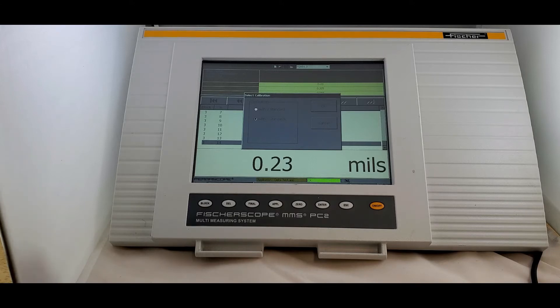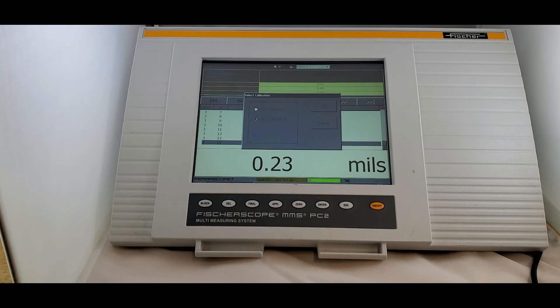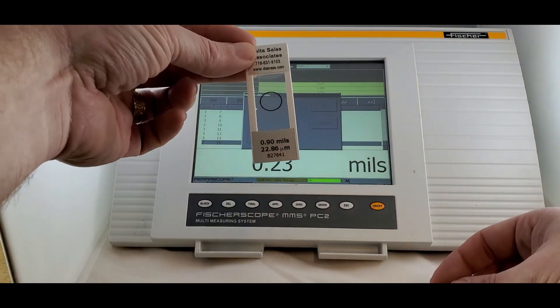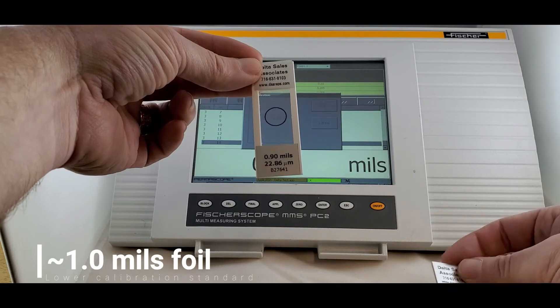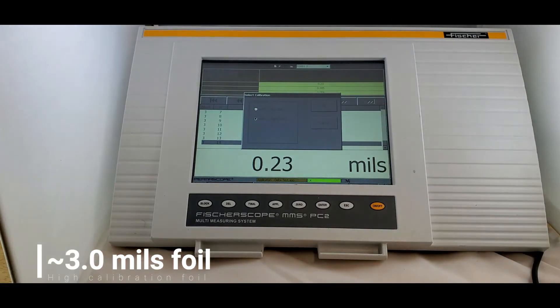You want to have two standards that are outside of your desired coating specifications. So for our purposes today, we're going to say that our coating specs should be somewhere between 1.5 and 2.5 mils. I'm going to work in mils just because that's how this unit's already set up. So what I've got for calibration is I have a 0.9 or essentially 1 mil foil, and then I have a 3 mil foil. That's just outside of the range that we're looking to do.